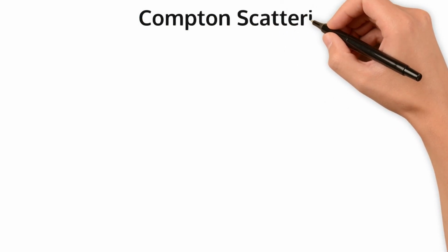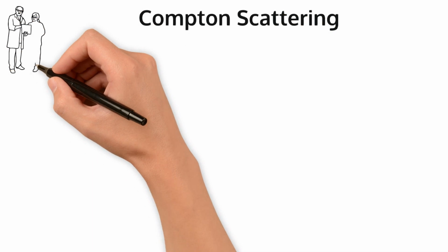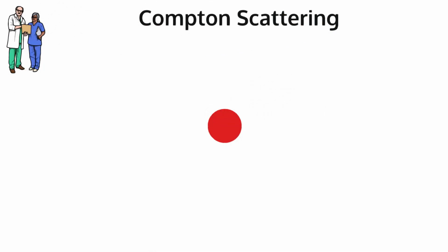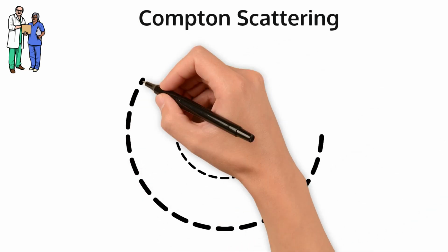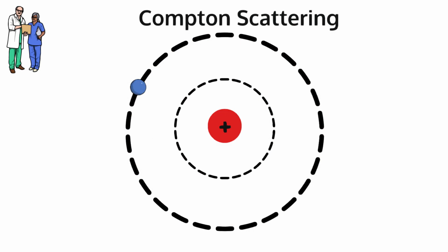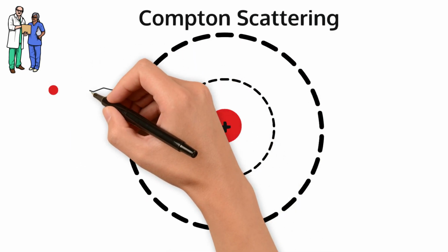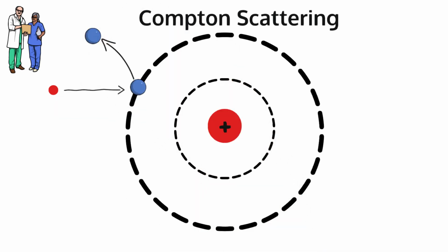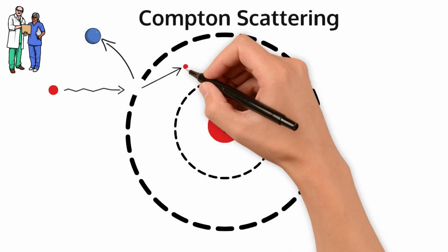In the production of X-rays, scattering also plays an interesting role. One such form is Compton scattering. This process not only needs to be considered in radiation dosage when the X-ray enters the patient, but also in their production. Photons produced in the generation may not immediately pass out through the X-ray tube and instead interact with other outer electrons or other metal atoms. In this process, a high-energy photon collides with a valence electron, ionizing it, and the photon is scattered and therefore has less energy than the incident photon.